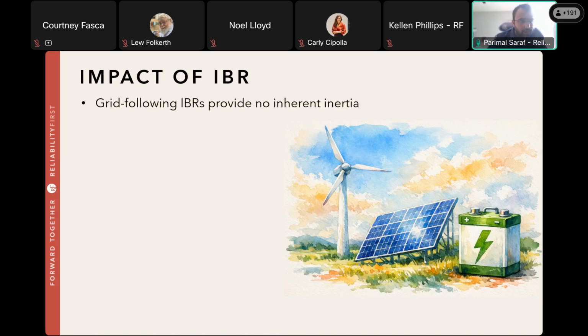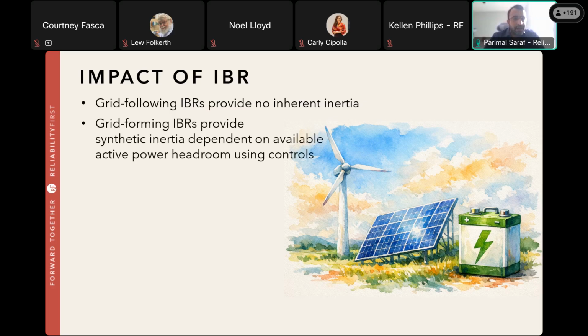So I don't see the text, maybe, yeah. So the first aspect, how the IBRs really impact the small signal stability of the electric grid, is through inertia. So traditionally in the electric grids, the inertia was provided through conventional synchronous machines that had a physical rotating mass. However, most of the IBRs that have been installed today on the field are mostly based on the grid following technology that inherently does not have the capability to provide inertia to the grid. The newly proposed grid forming technology does have capability to emulate or provide synthetic inertia, but it requires the IBRs to have active power headroom in order to provide that feature or capability. So that's again restrictive in some form or aspect.